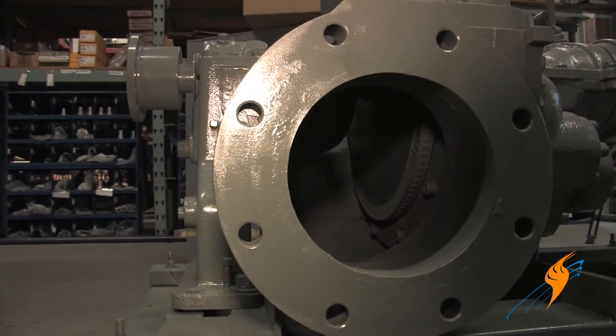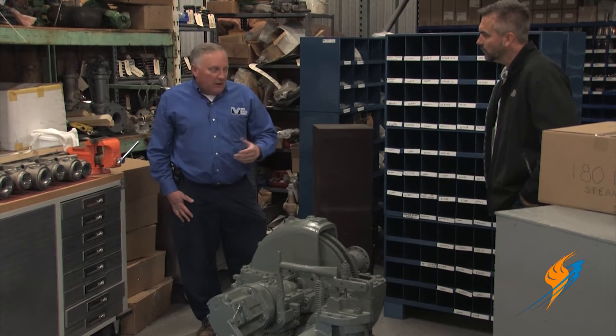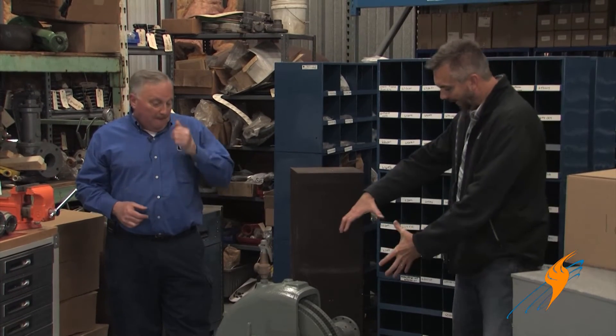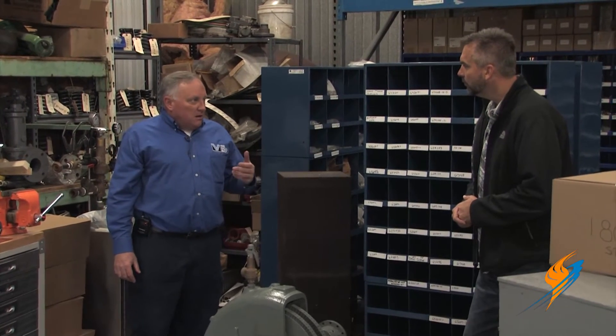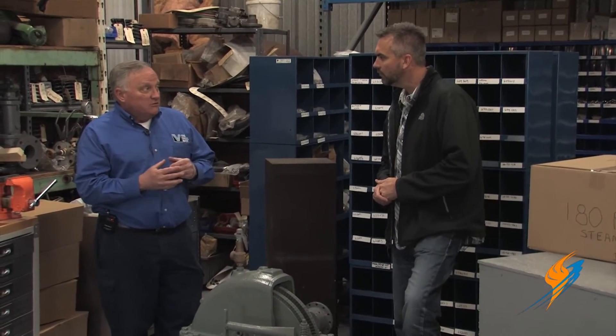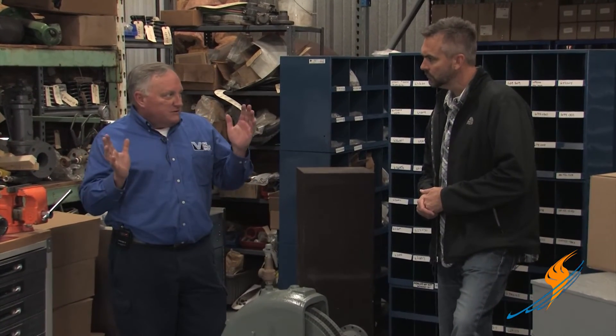We're going to lose a little bit of BTU content when doing this, but the value of the motive power far outweighs the cost of the steam we'll lose. The 20-pound steam goes to whatever we normally had it going to — a 20-pound header, a big heat exchanger, a number of different devices. Off the back we can have a generator, a fan drive, an air compressor, or a pump. We are picking up that energy which is lost in that pressure reducing valve. If you walk by a PRV that's flowing really heavily, you'll recognize the energy loss because it's really loud — it's screaming. We're losing that energy in noise and in damage to the valve.